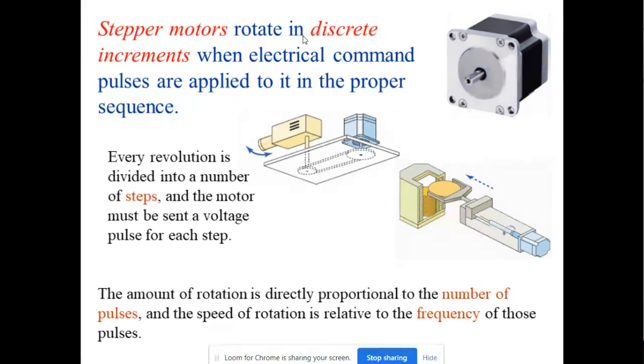Stepper motor. Basically, it rotates in discrete increments when electrical command pulses are applied to it in the proper sequence. Every revolution is divided into a number of steps and the motor will be sent a voltage pulse for each step. The amount of rotation is directly proportional to the number of pulses, and speed of rotation is related to the frequency of the pulses. These are the stepper motors.